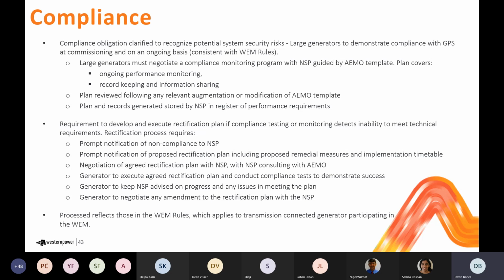So there's a template there that AEMO needs to produce, and the technical rules require that any compliance monitoring program produced under the technical rules must also comply with the same template. And so what you're seeing here are very similar to the GPS arrangements. If you're a large generator, you'll either have a compliance monitoring program established via the WEM rules process, or you'll have one established via the technical rules process. And because they reference back to the same template, they'll be quite similar in either case. So there's no particular difference that should result from establishing your compliance regime via the WEM rules or the technical rules.